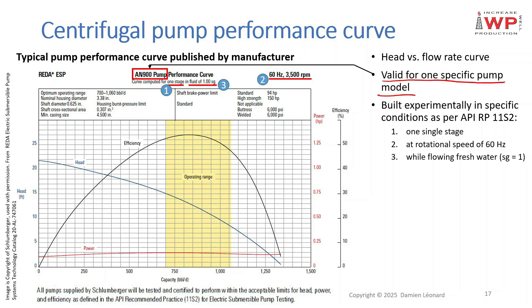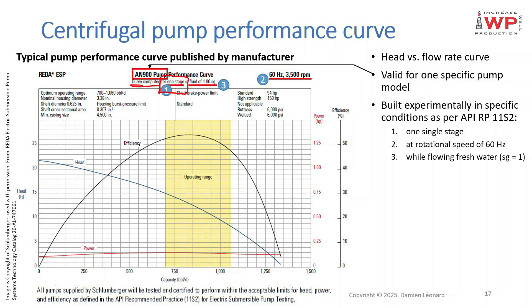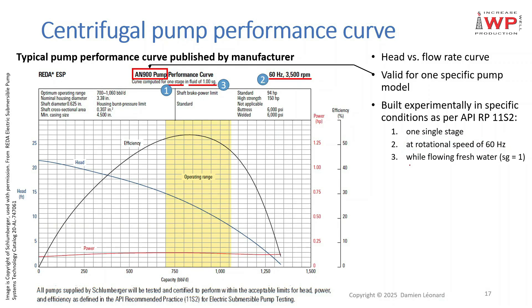This type of curve is valid for one specific pump model — in the example chosen, it is the pump AN 900. These curves are built experimentally per API Recommended Practice 11S2: using a single-stage pump, at a rotational speed of 60 Hz (corresponding to 3500 RPM), while flowing fresh water with a specific gravity equal to 1.